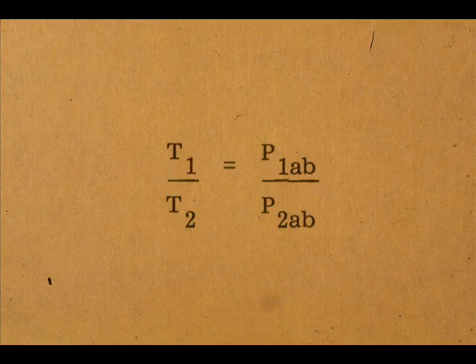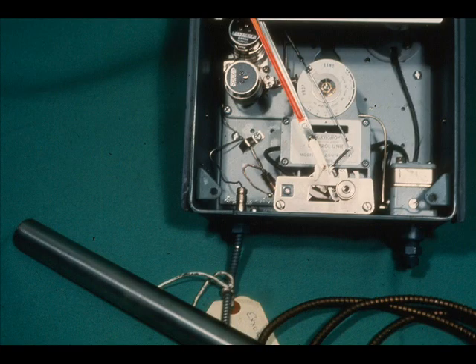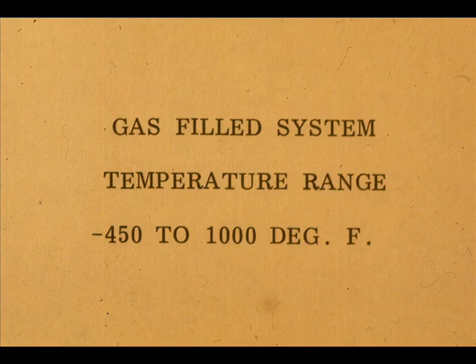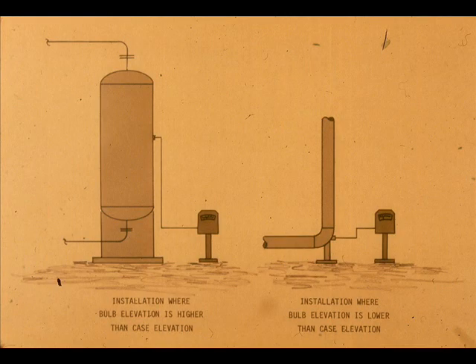Since a change in absolute pressure of a confined gas is directly proportional to any change in absolute temperature, gas-filled thermometer systems are considered to be one of the most accurate methods of temperature measurement. They have a very wide operating range, have linear readouts, and are unaffected by differences in case and bulb elevations.